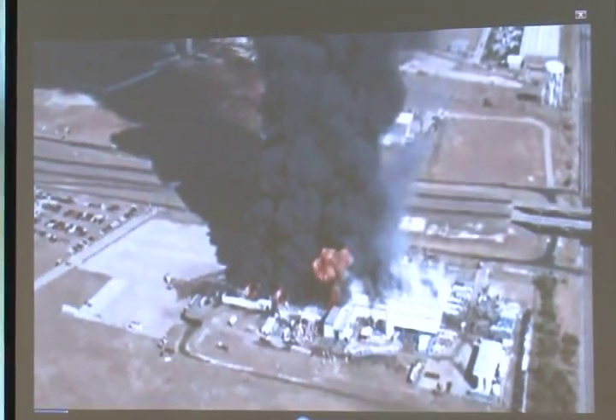All right, this one's going to be the Magna Blend fire in Texas 8 months ago. I'm going to show this because, for those of you that do store flammable and combustible liquids, besides just knowing flash points, you also have to know if they are water-soluble flammable liquids or non-water-soluble flammable liquids. For water-soluble flammable liquids, a water sprinkler system will work fine. For non-water-soluble, the fire will float on the sprinkler water and spread all over the place. So you have to think about, do I need a foam water sprinkler system in that case?